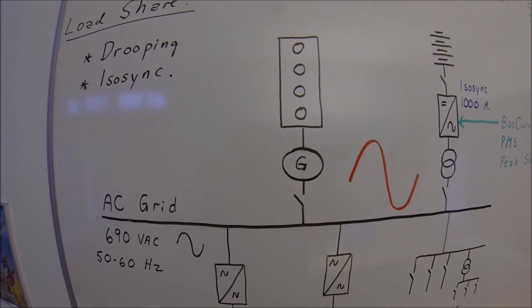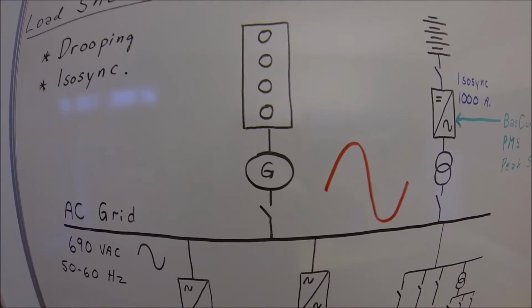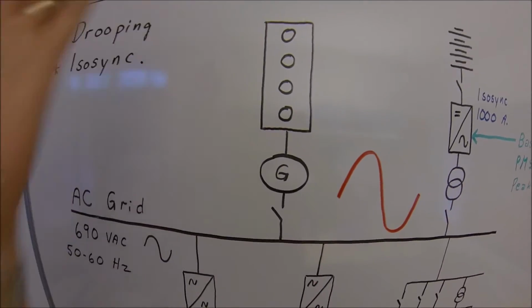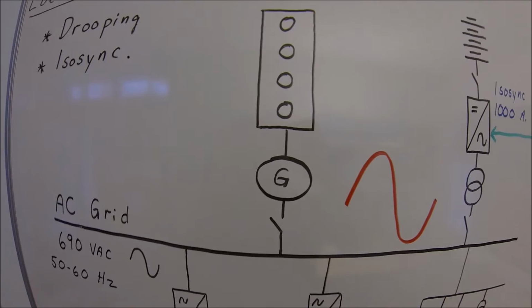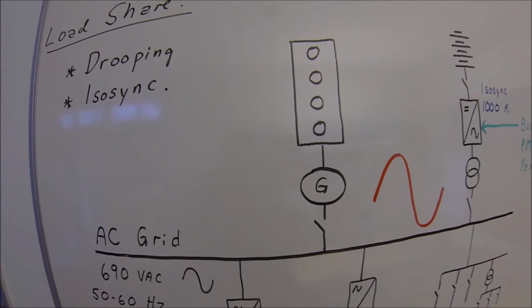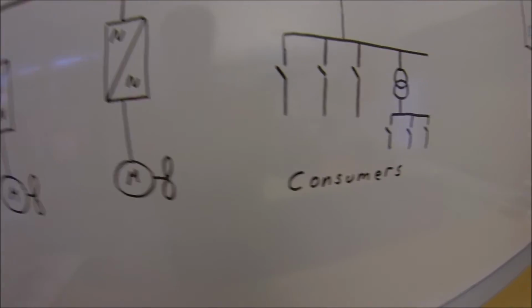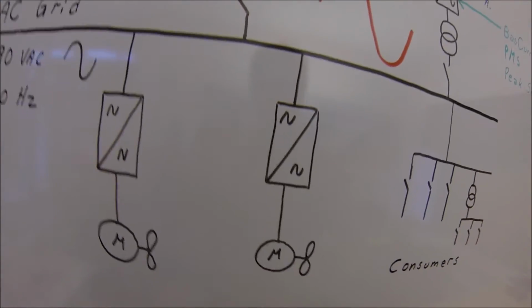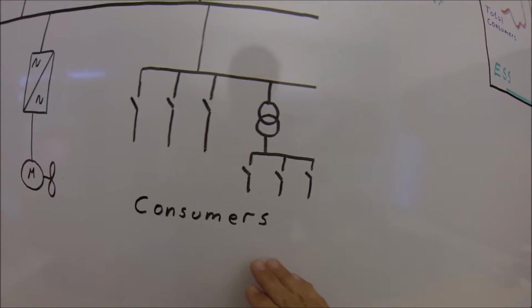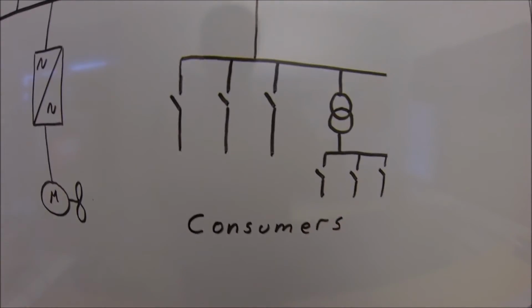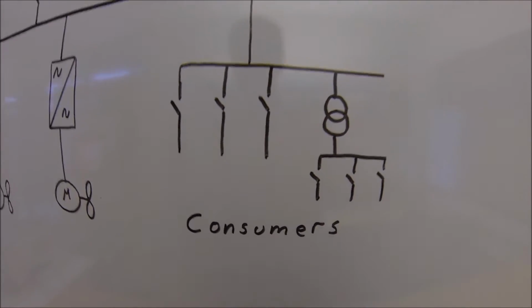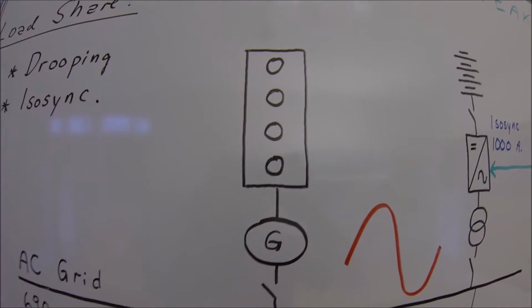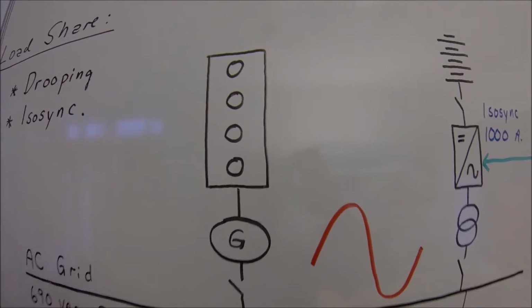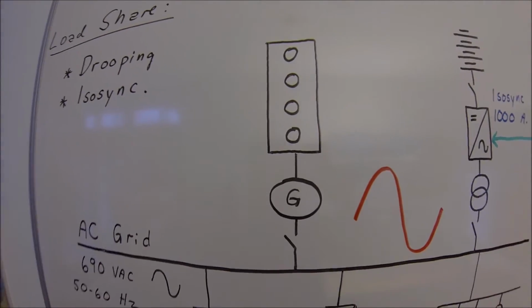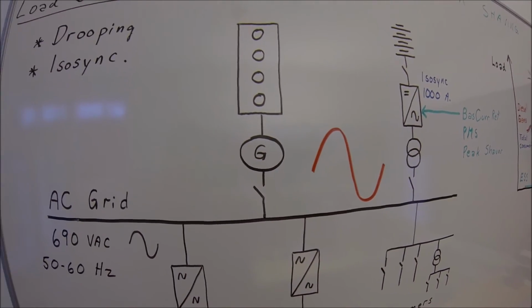Pure diesel, marine gas oil, have a quicker dynamic, maybe 100 kilowatt per second for a 2 megawatt generator, but with liquid natural gas, because of the manifold and fuel system, it's really, really slow. So you don't want one of the consumers to put on a big load in a very abrupt way. If you have a direct started thruster, there is a compressor or hydraulic power plant which can suddenly take 500 kilowatt in a second, then the only way to deal with this today is to have many, many diesel generators running, to have a spinning reserve, to have a lot of margins to cope with these huge changes.